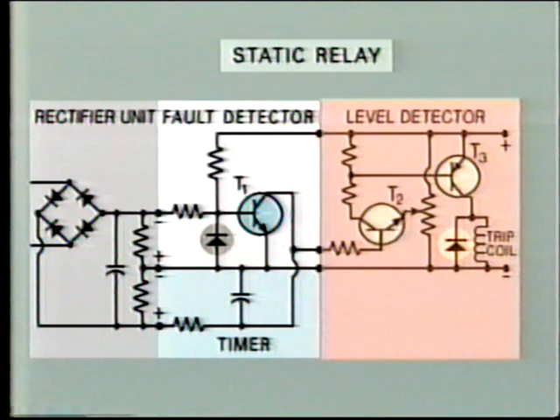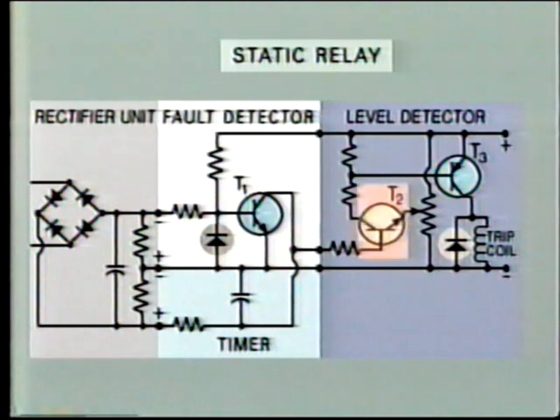Now, we'll connect the trip circuit to the output of the fault detector and timing circuits. This second transistor here is used as the triggering circuit for the output transistor. The emitter voltage is adjusted by this variable resistor. When the timing capacitor voltage exceeds the emitter voltage by a predetermined amount, this transistor will start conducting, and this in turn will operate the output transistor and thus trip the relay.